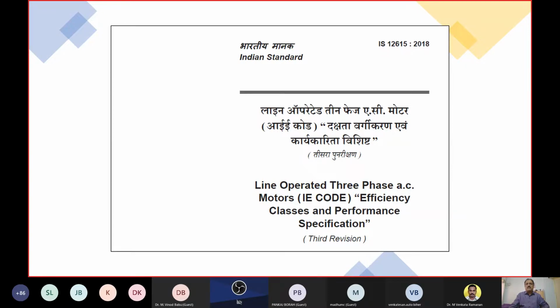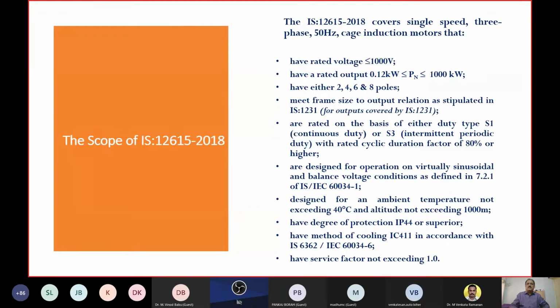So efficiency values are declared. Some of the performance values are also covered by this standard. The Indian standard is the only standard where performance values like starting current, pull-out torque, starting torque, etc. are mentioned in the standard. This is for protecting the interest of the consumer. Then let's take a look at the scope of this IS 12615.